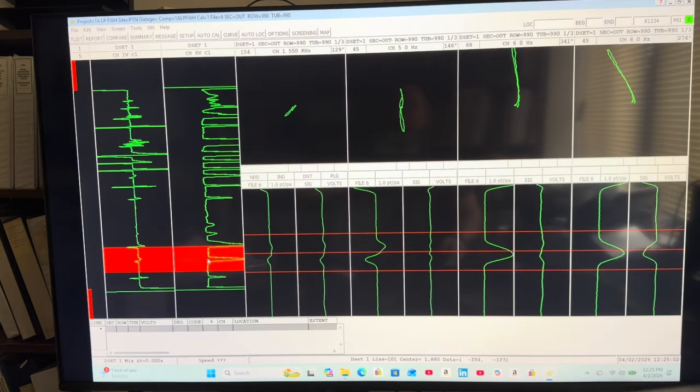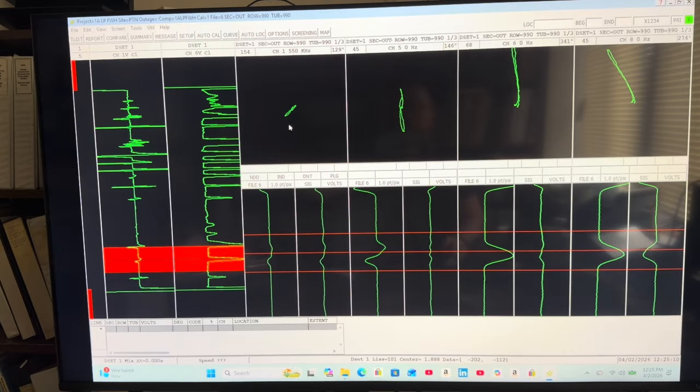Then I've got some sort of buffing wheel here, which, let's see what that is. It could be that. Obviously that must have had some abrasive quality to it because it did introduce an OD flaw. Notice that rotates counterclockwise with decrease in test frequency. Also, the absolute signals are very pronounced.